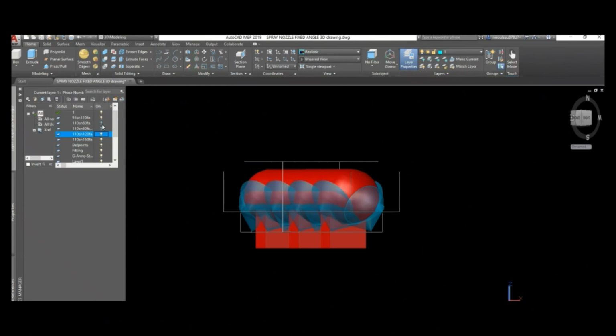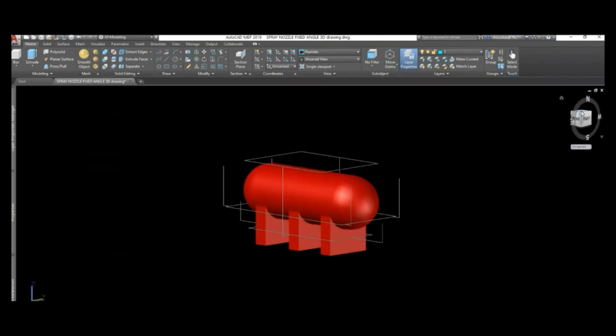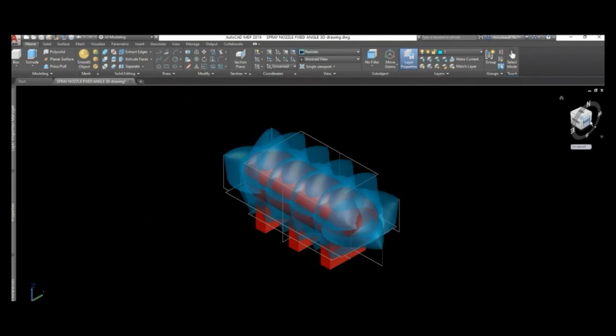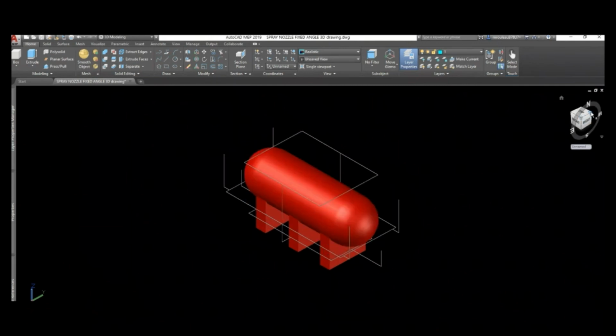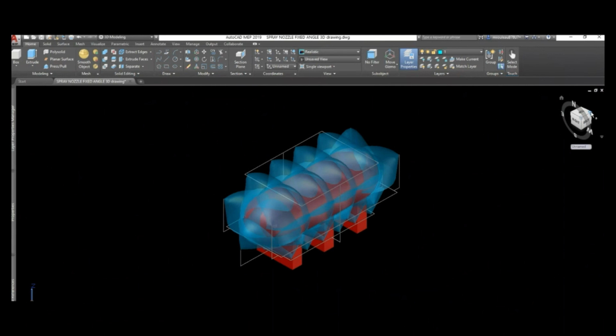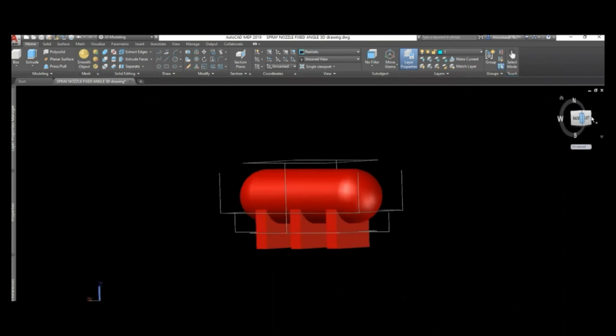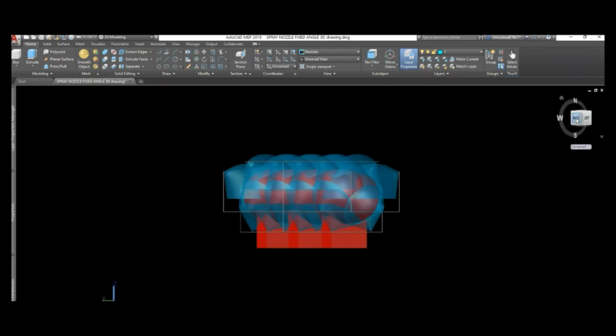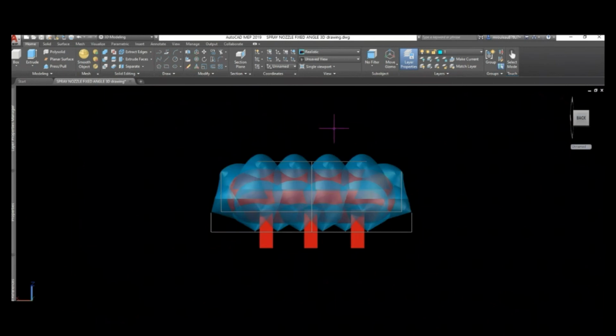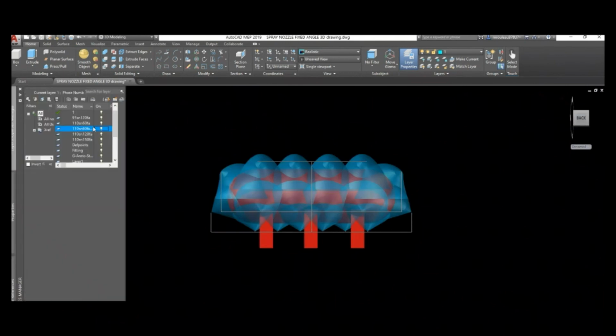So you can see as we're working our way around here, we just select different nozzle discharge patterns, orient them at different orientations, straight down, to the side, up from the bottom, and again, you can then essentially look for gaps in your coverage area, very easily shift things around, make sure that the flow is doing exactly what it needs to do.